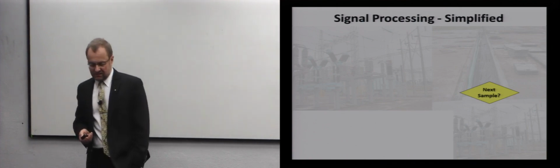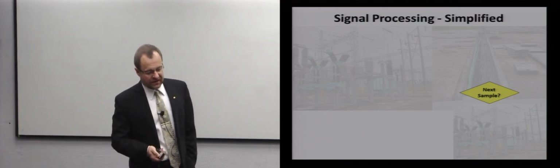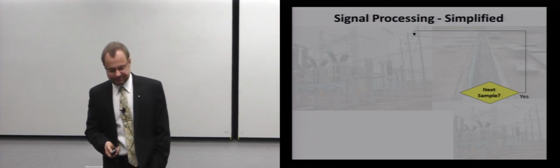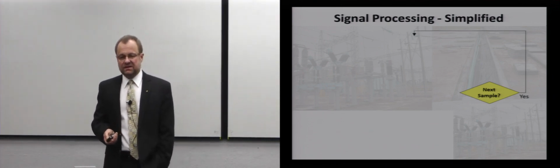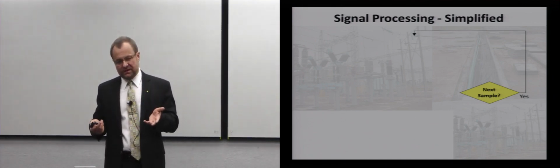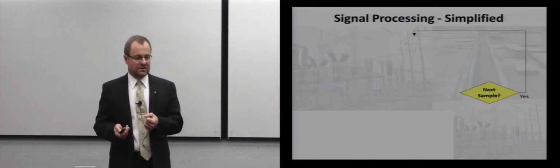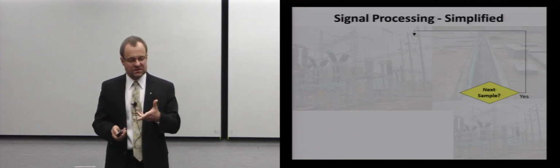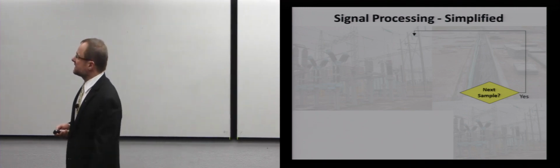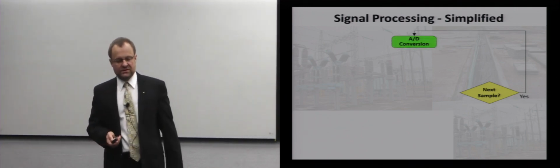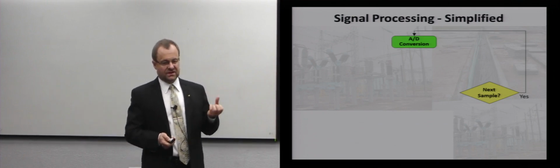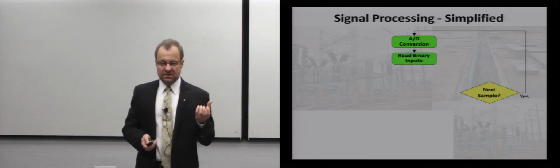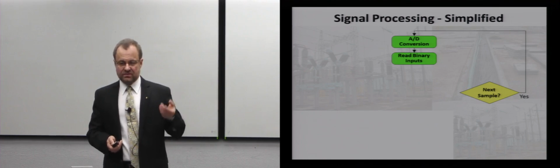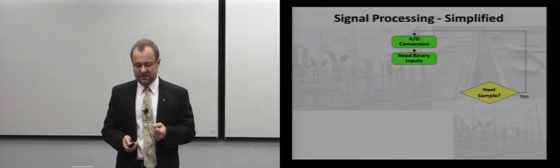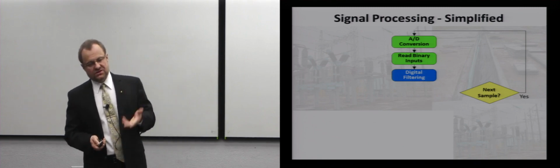Now, signal processing. If you were to simplify it, you would think that it works like this. You wait for the next sample. So for example, you decided to sample your input signals at the rate of 2 kilohertz, right? So every half a millisecond, you will take a new sample. So you wait for a new sample, you got it. Then you do an A to D conversion. So now you got a number that represents your input. Then what you may do is read the binary inputs. Is the input high or low, asserted, deasserted, right? Those are your inputs. Then you do digital filtering.